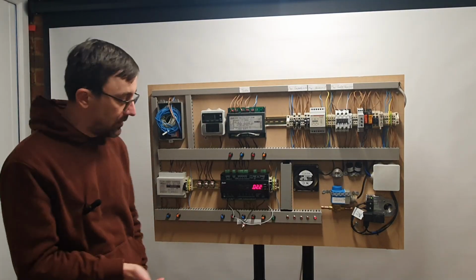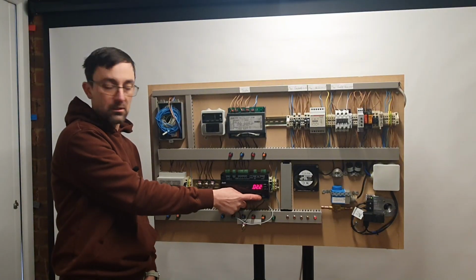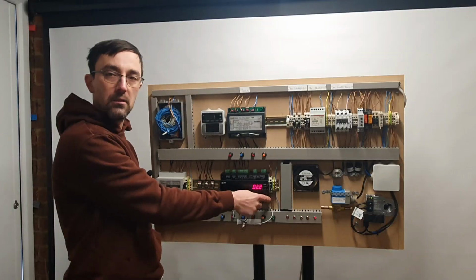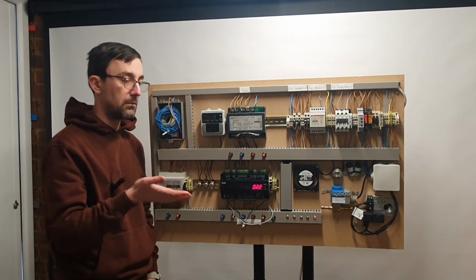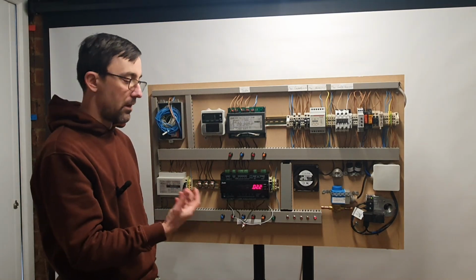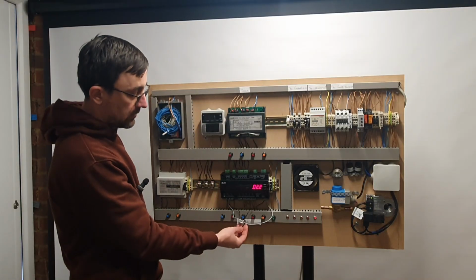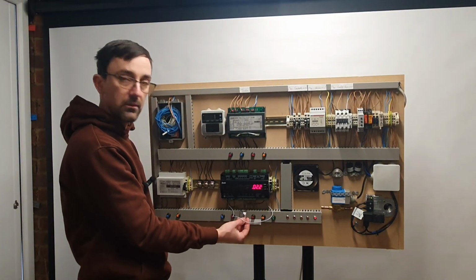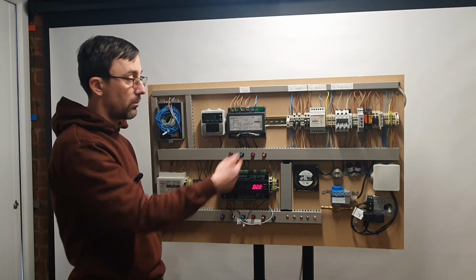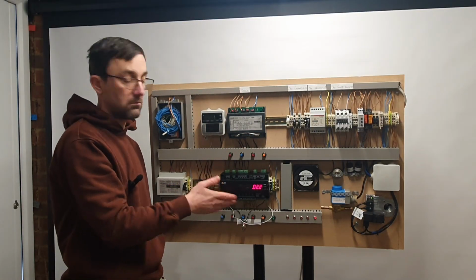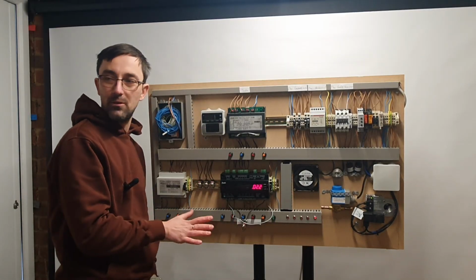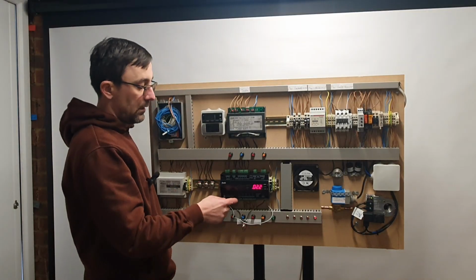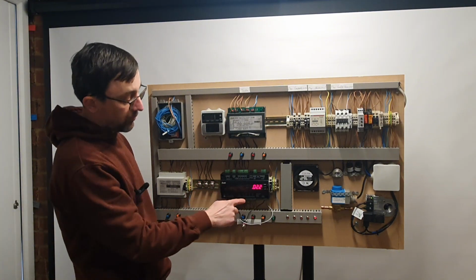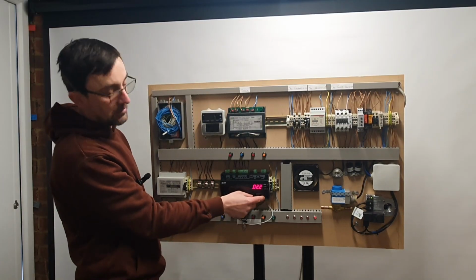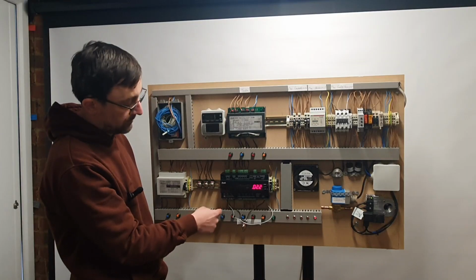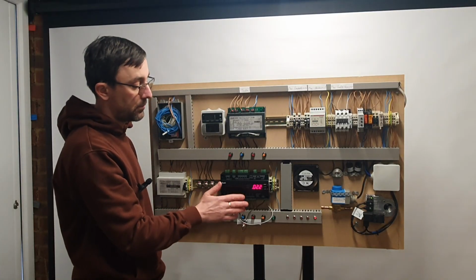So the way I tried to wire it initially is 230 volts goes into the first connection of the digital input and then comes back into the second connection if the contact is closed. So that means I have continuity on the contact. That didn't work. So then I thought maybe it's a live and a neutral. So I wired the switch for my thermostat band. If I want to do a switch over, 230 volts goes into the switch from an external source. As a test, I chose the supply source. Don't try this on site. Again, this is a controlled environment, so we can do that, in my opinion. So 230 volts comes into the switch and comes out from the switch into the first connection of my digital input. Then the second connection of my digital input is a neutral. And it seems to be working. So maybe that's the way it's supposed to be wired.